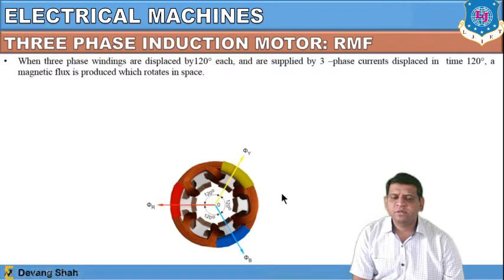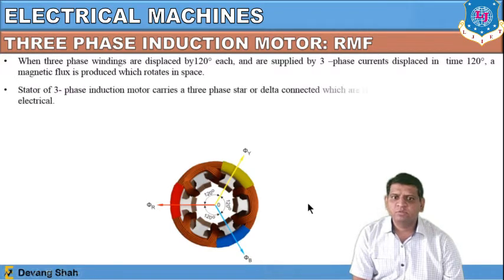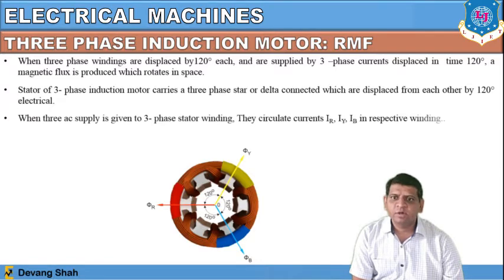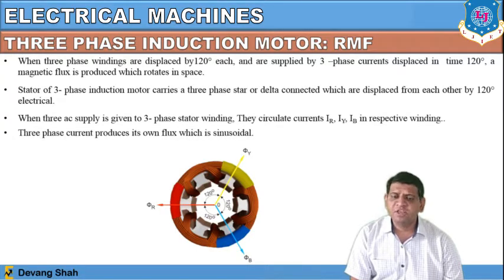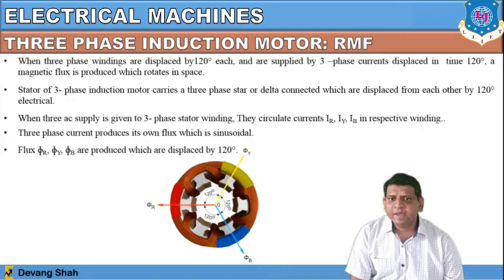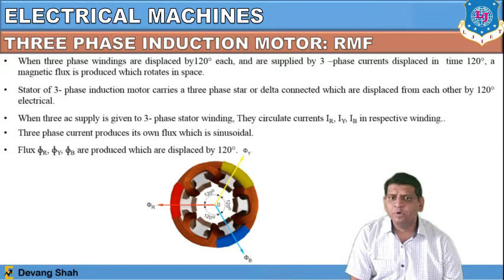Once you apply the three-phase AC signal, this particular winding will produce a rotating magnetic field where windings are 120 degrees apart. The stator of the three-phase induction motor carries three-phase star or delta connected windings displaced from each other by 120 degrees electrically. From that, we apply three-phase AC signals in the form of currents IR, IY and IB, which produce magnetic fluxes φR, φY and φB — all displaced 120 degrees apart from each other.